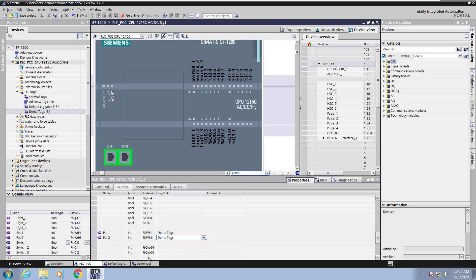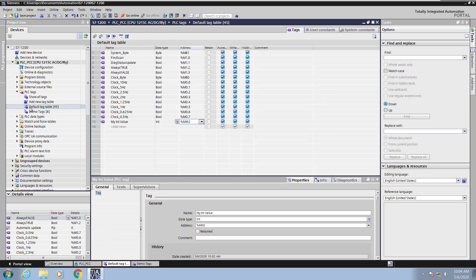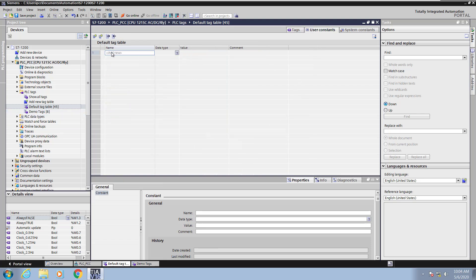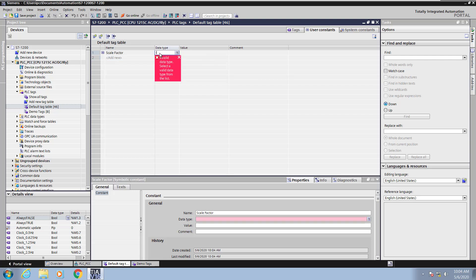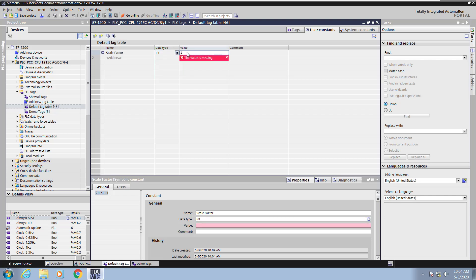The QW addresses would be for the analog outputs but I will not enter in any tags for those now. I'm going to open up the default tag table and select the user constants tab. Here you can create constants that will contain a value used throughout the program. I'm going to create one called scale_factor, select the data type as integer, and give it a constant value of 2. So scale_factor can now be used throughout the PLC program.